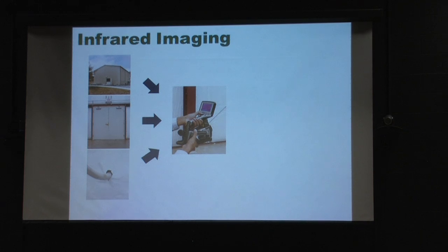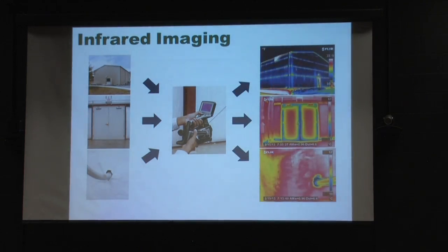These photographs were taken of the same building, same end. In the top image you can see exactly where the girts are in the building—where the steel structure is and where the insulation is draped, giving a continuous line of thermal bridging. We don't have enough insulation there. This camera is sensitive enough to pick up the screw holes, showing the leaks exactly where the metal exterior is screwed on.